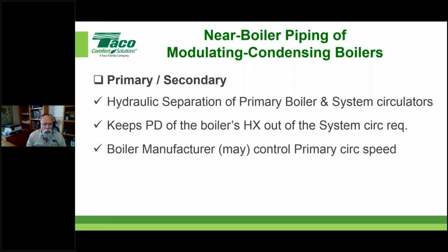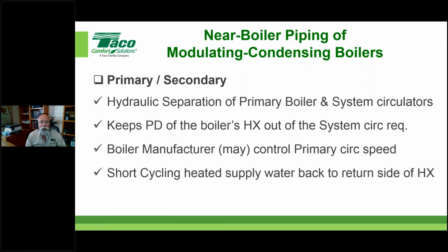Okay. So anyway, the boiler manufacturer nowadays can and may control the primary circulators, that's the boiler circulator, that can control its speed. We'll talk about that a little bit as well. And if we can do that, we want to do that and take advantage of that as well. One of the downsides of primary secondary piping is you have the possibility of short cycling water from the supply pipe that goes into the closely spaced T's backwards, I should say, and back up and into the boiler. And this will happen on some occasions. What we're trying to do with this little session is make sure you keep that to a minimum. Okay, and we'll show you what that looks like.